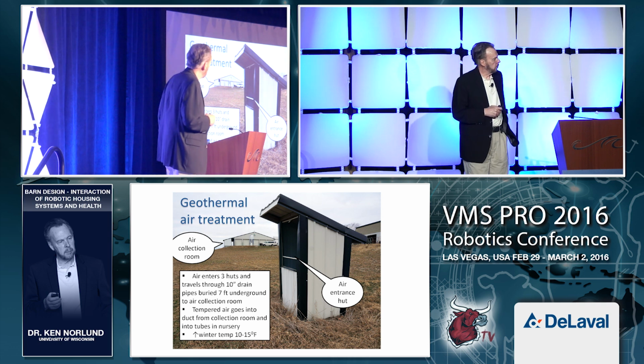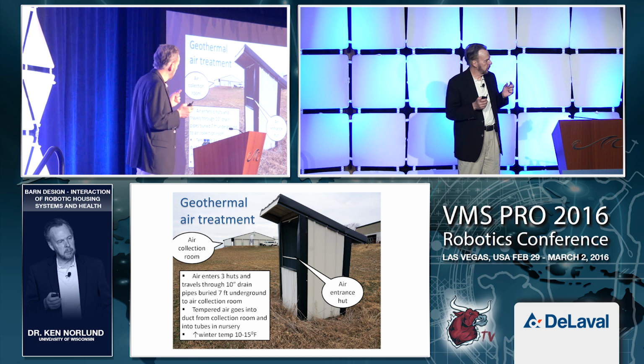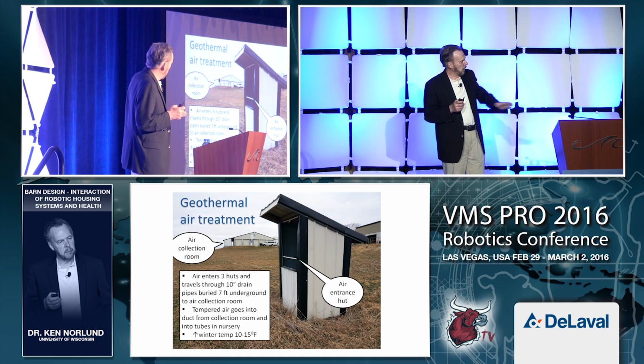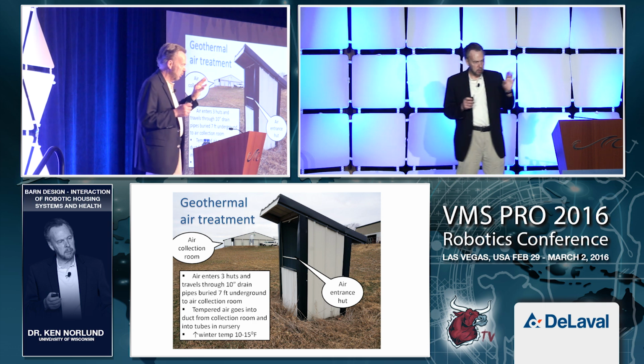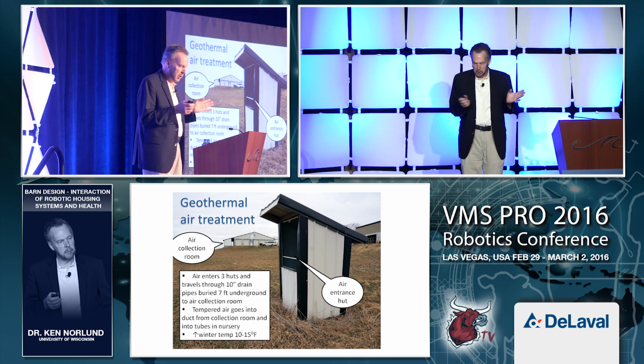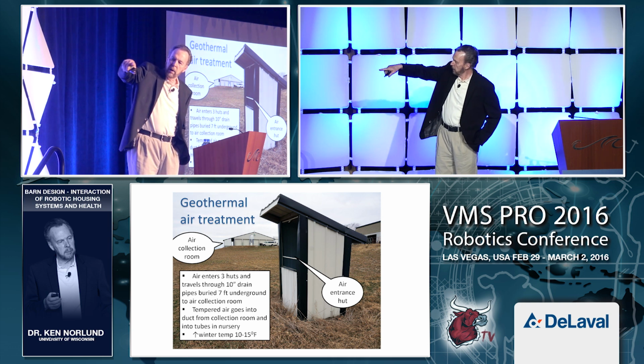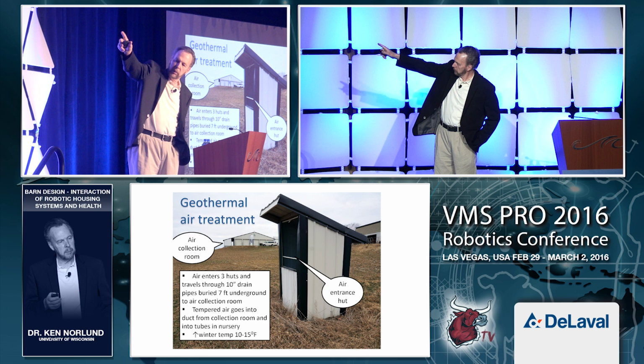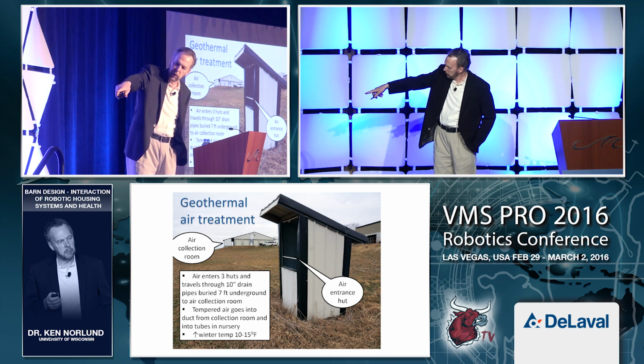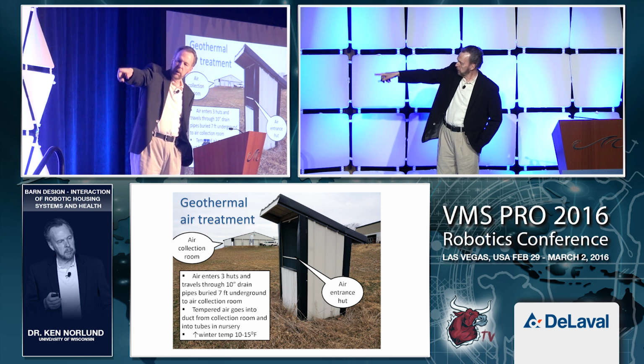Again, this is a barn in Wisconsin that is using geothermal ducting, buried pipes to warm air that goes into a positive pressure tube system in a calf barn. And again, some of you may be interested in it. They actually have 3 little huts like this where air enters the hut, and there are pipes, flexible plastic pipes that go down. They're buried 7 feet down. They run about 200 feet to the barn. There are actually 6 buried pipes.